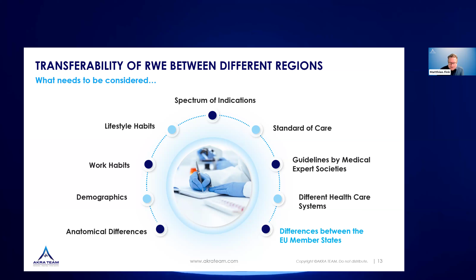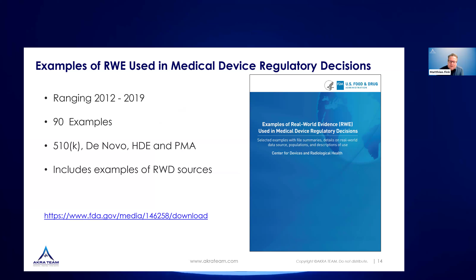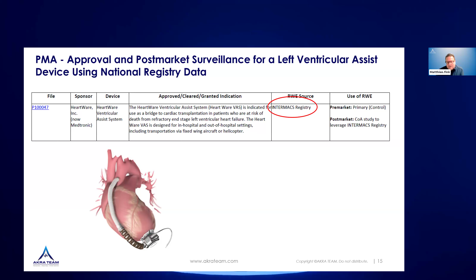To provide some examples, the US published in 2019 this list of 90 examples for 510(k), de novo and even pre-market approvals, meaning talking about class 2 and class 3 devices. I couldn't find an updated version, so I think it is still the latest they have. But these are examples where the FDA basically accepted real-world evidence, at least partially, as clinical data. One example is left ventricular assist device. As you can see, the real-world data source was the INTERMACS registry, which is the big US registry that basically collects data on all patients that require mechanically assisted circulatory support, which is usually an LVAD or a BiVAD or even a total artificial heart.